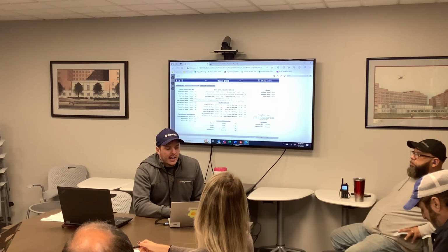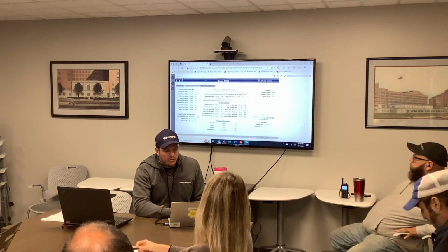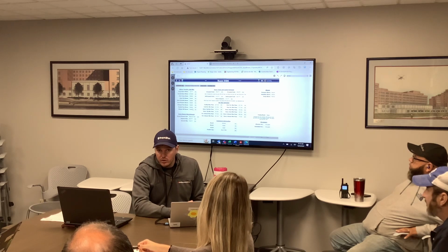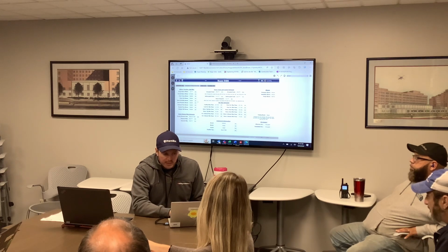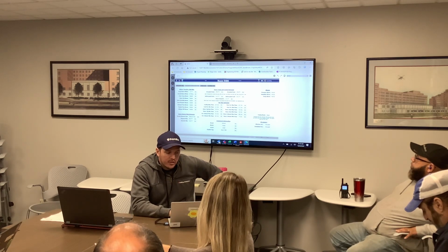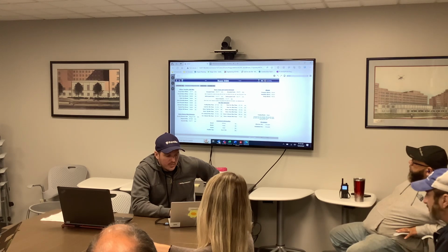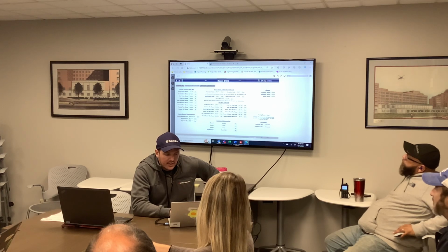Right now, I have all the alarms disabled. You guys can come in here and turn on any alarm you want. I don't know what alarms you want, you can specify. I gave you all the options and you can just enable them. For the temp, here's the offset: if it's 5 degrees above or below set point, it's going to trigger an alarm. Same with humidity at 20% relative humidity. Just like the VAVs, you can disable the local stat, and the min and max they can currently set it for is 85.